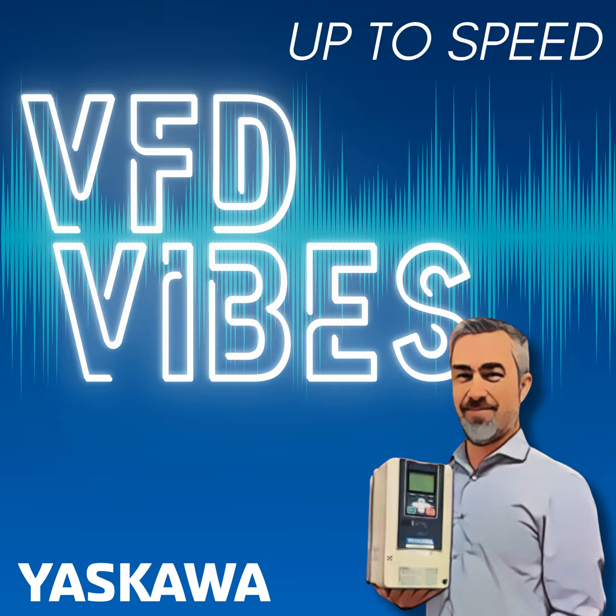There's capacitance to ground. That capacitance is there to bleed off the high-frequency signals. Well, it doesn't actually go to ground. It goes to the back panel of the cabinet. I had a situation where there was a lot of EMI that was trashing the PLC that was also in the cabinet, and the cure for that was to remove the EMI filter, because all the EMI filter was doing was capacitively coupling the noise that was on the input to the drive right back into the back plane of the panel. So we had to take that filter out, or at least bypass it.